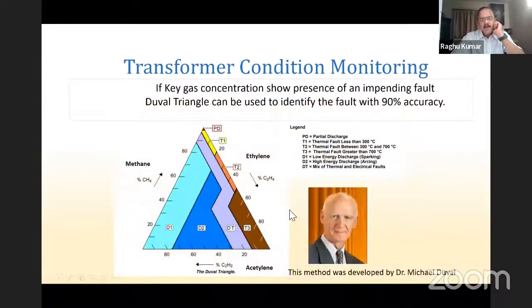In the Duval triangle, he has given a triangle with three gases: methane, ethylene, and acetylene. Percentages are calculated on a three-coordinate basis, and where the three coordinates meet at some point in this triangle, that is the fault. These faults are given as D1, D2, DT, T3, and all these are explained here. Suppose it meets at D2, it means it's a high energy discharge, like that ethylene concentration issue. And if it meets at this point, it's a partial discharge.